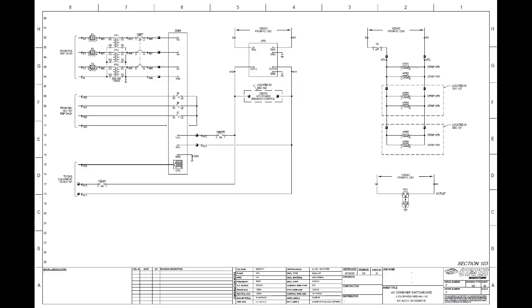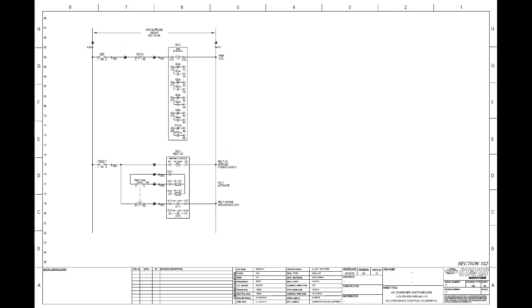As I said, with the way our UL procedures are written, we can tailor those internal components, whether you have a customer requiring a specific digital meter, a specific UPS to provide power, or if they just say make sure we have power for our control components for an hour, 2 hours, 3 hours, 4 hours, whatever it may be, we can design your control system to meet whatever your needs are.